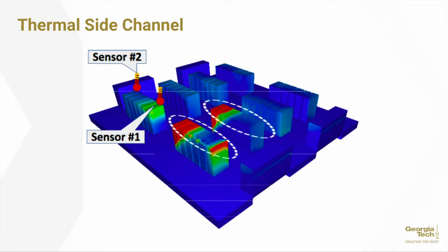So the heat from the first server will travel over some space and time and reach the other server. This can be detected by temperature sensors on the air intake of the other servers, and it's also modelable by using fluid dynamics to model the flow of this heat throughout the data center.